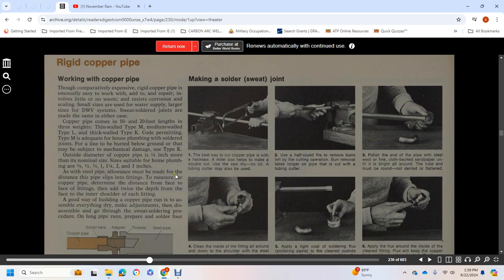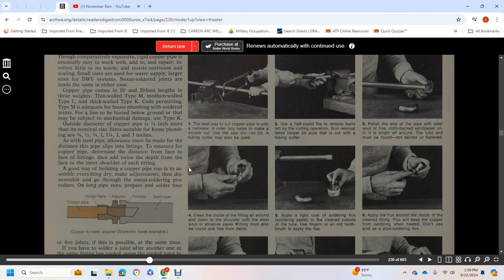As with steel pipe, allowances must be made for the distance the pipe slips into the fitting. For copper pipe, determine the distance face-to-face of fittings, then add twice the depth from the face to the inner shoulder of each fitting. A good way of building a copper pipe run is to assemble everything dry, make adjustments, and disassemble. Go through the sweat soldering procedure on long pipe runs.